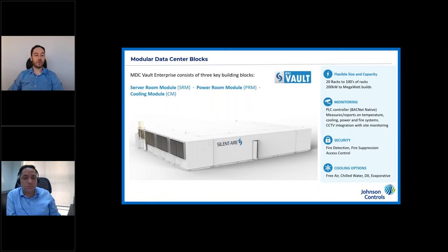If we consider the main part one would use for one's own capacity, or the capacity of the data center sold in co-location in the co-location industry, that would be the server room modules. The white floor space inside these units is often, in the way we build, constructed in hot aisle containment or cold aisle containment.